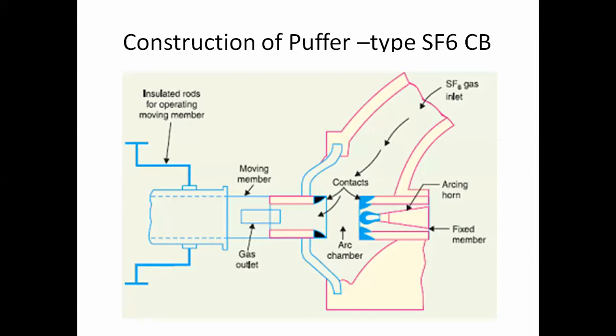But whenever an arc is generated, or a fault occurs in the system, the moving chamber gets separated from the fixed chamber, and you can see that between the moving chamber and the fixed chamber there is an SF6 gas inlet, and the gas gets inserted inside this chamber. Whenever an arc is generated in the arc chamber, the SF6 gas, since it is inert and non-flammable, deionizes the arc components, and hence the arc is extinguished in the shortest possible time. When the arc is extinguished that quickly, the temperature of the circuit breaker stays under normal conditions, and it will not affect the circuit breaker or the system.